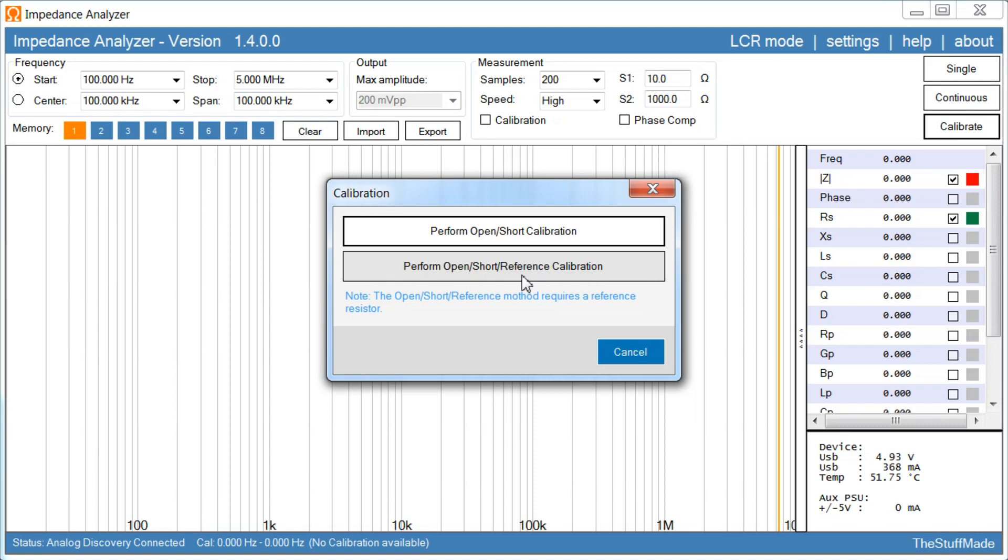It is quite important to use an SMD resistor, something like an 805. Let's say you want to do a capacitor measurement, something like, for example, a 1 ohm resistor would be a good value for that measurement. Anyway, I will just do the quick open short calibration for this demonstration.